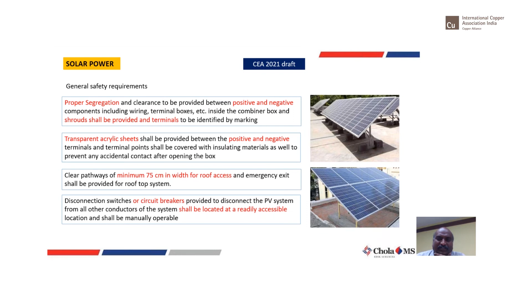There should be a clear space around the solar panel that you have installed on your roof for people to move around, and the standard calls for a minimum of 75 centimeters. You should have a proper disconnect switch and circuit breakers at the DC level, located in such a manner that they are easily accessible. It should not be that a person has to search for a stool, bring that stool and then disconnect it. No, it should be easily accessible.